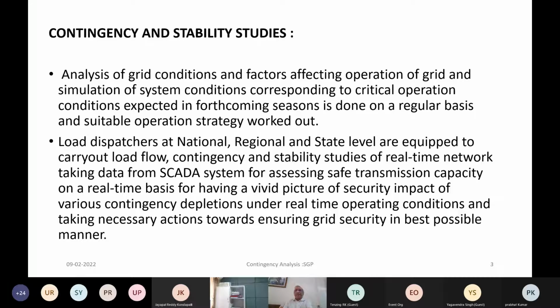So analysis of the grid conditions and factors affecting operation of the grid, and simulation of the system conditions corresponding to critical operating conditions, is expected to be done on a regular basis, and a suitable operation strategy is to be worked out. This is the role of the load dispatch center. Generally, this is done based on real-time data from the network every day. State estimation and load flow programs are run periodically, and with respect to line loading, etc., it is ensured that adequate margins are available if any unforeseen tripping happens. And in case a tripping happens, what the new condition of the grid will be can be found out by running such a study.